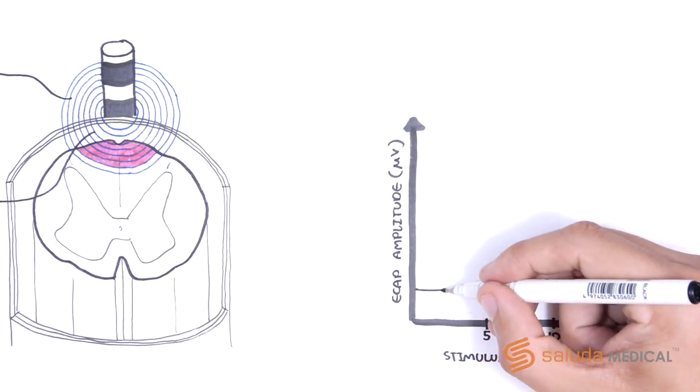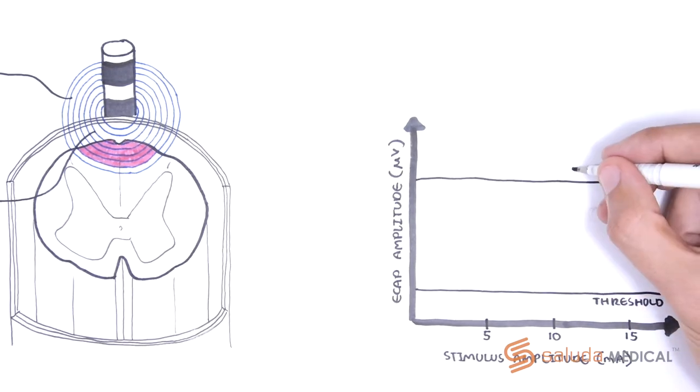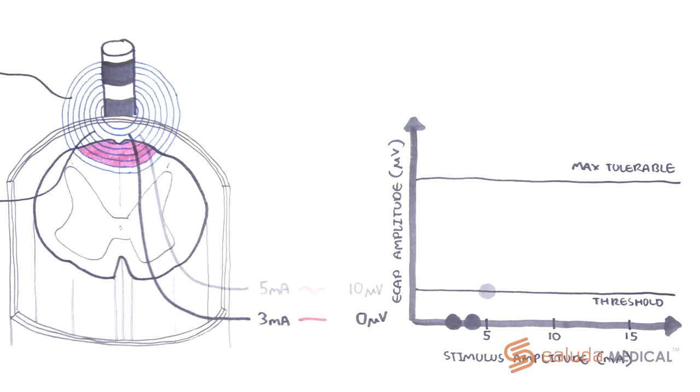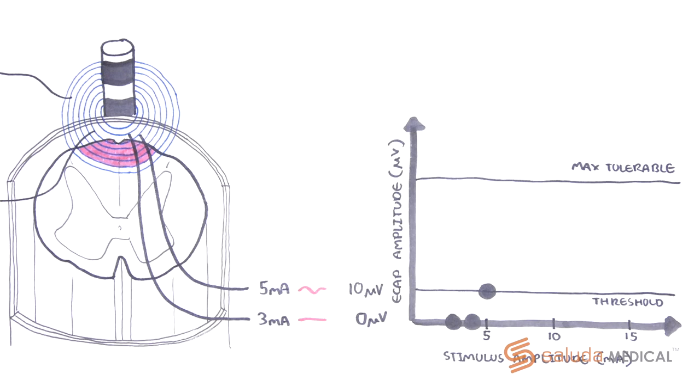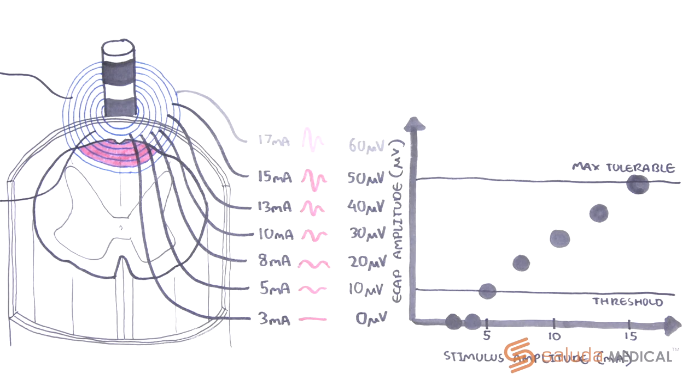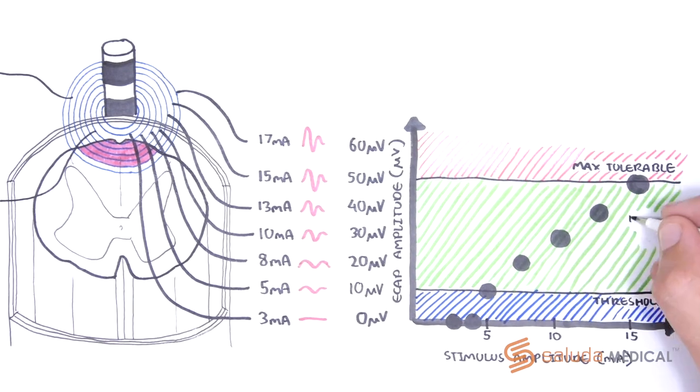This can be achieved by measuring an activation plot, with ECAP amplitude plotted against stimulus amplitude, where the patient reports when they first become aware of the stimulation, referred to as a perception threshold, up until the moment the stimulation becomes uncomfortable, referred to as a maximum tolerable. In this example, 3 mA and 4 mA stimuli generate no ECAP and no sensation. However, as the stimulation is increased, the patient reports some sensation at 5 mA. The ECAP is detected and the ECAP amplitude increases linearly until 15 mA, where the patient notes the stimulation becomes uncomfortable. We can label our measured upper and lower bounds. The range within these bounds comprises what we call the therapeutic window.